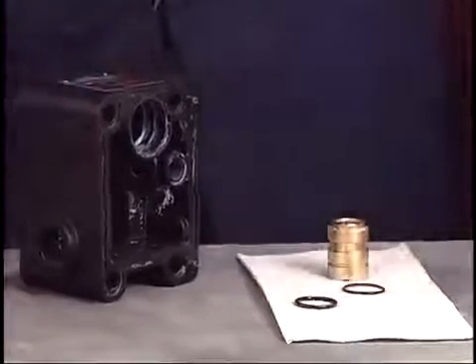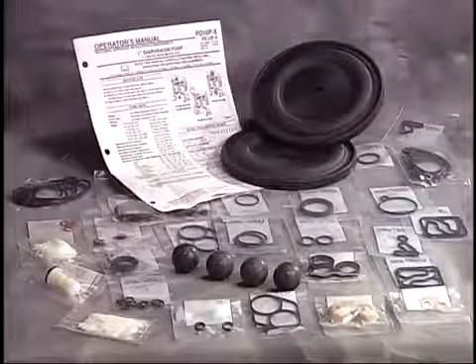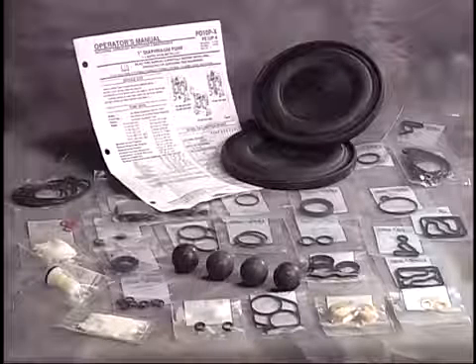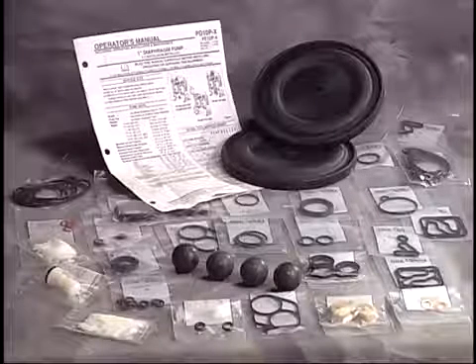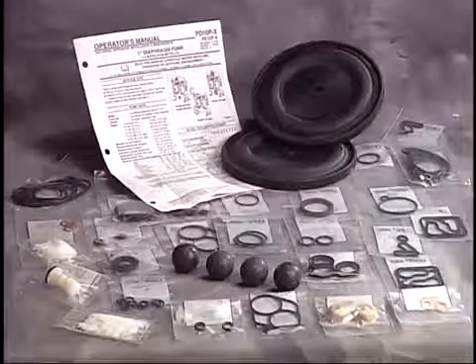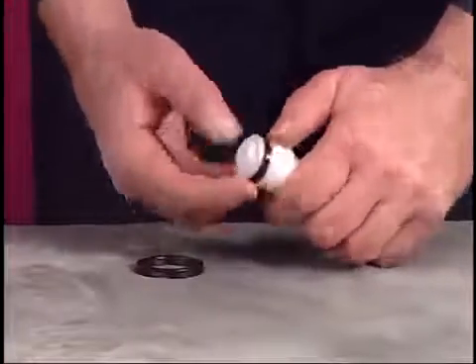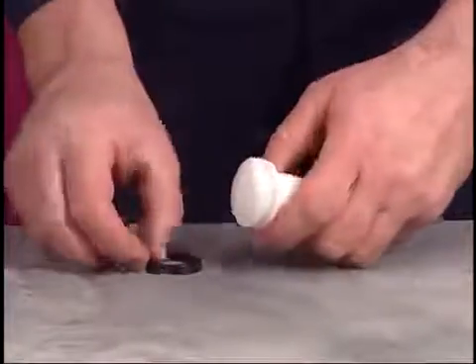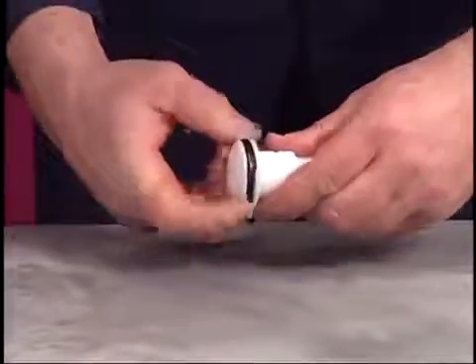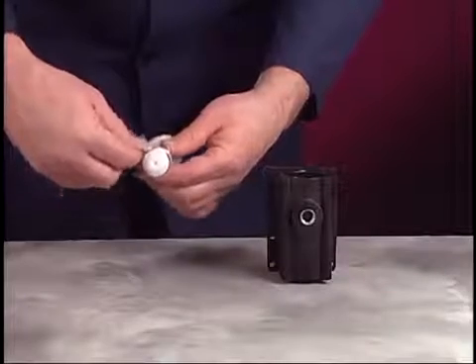Clean all components prior to reassembly. Use ARO service kits when repairing the pump. Apply Lubriplate FML2 grease to the O-rings and U-cups prior to reassembly. A packet of grease is supplied in both service kits. Install new U-cups on the spool, making sure the lips of both U-cups face toward the center of the spool. Lubricate the spool assembly and the internal diameter of the valve block.